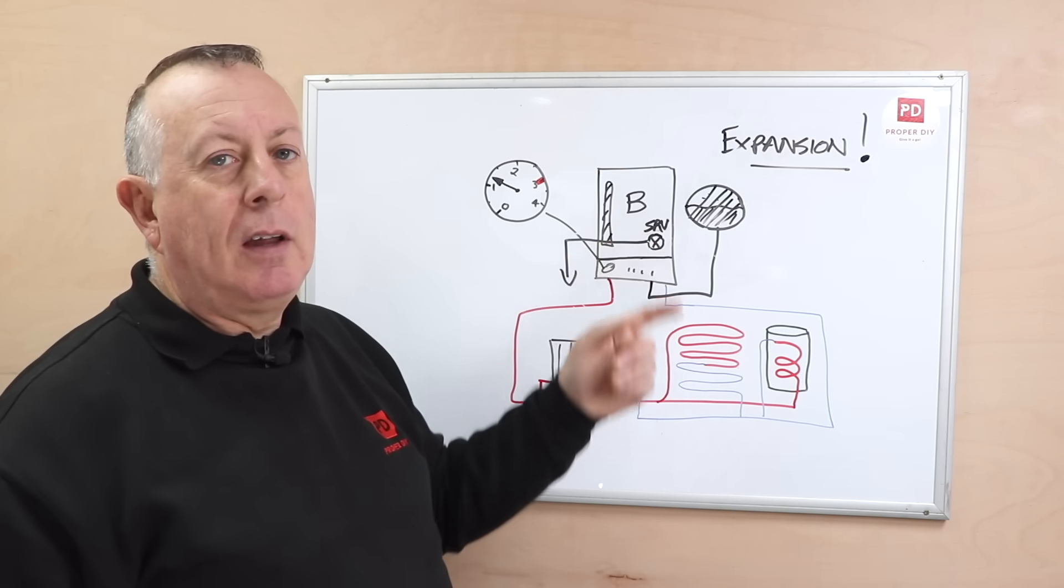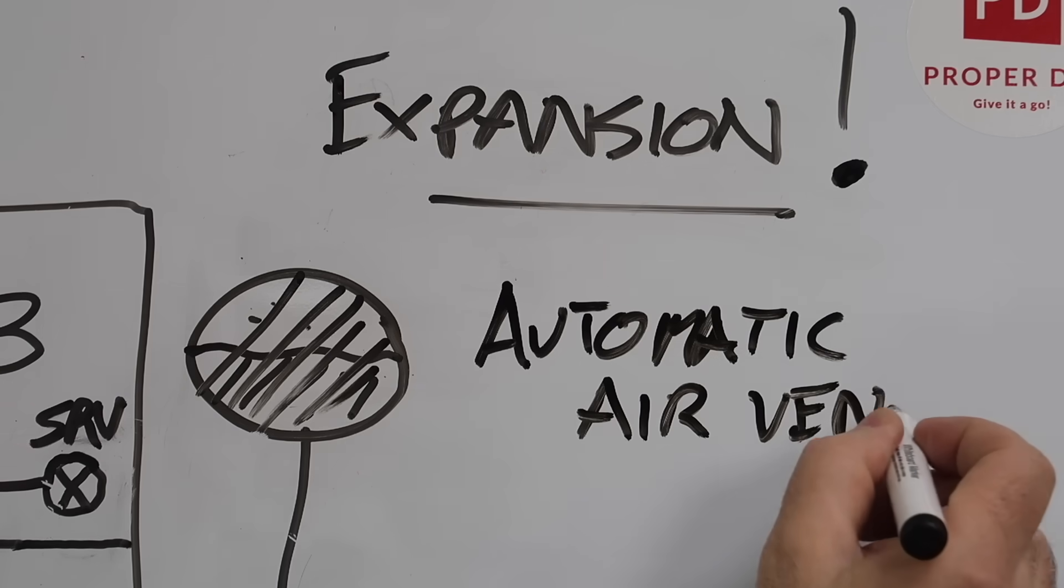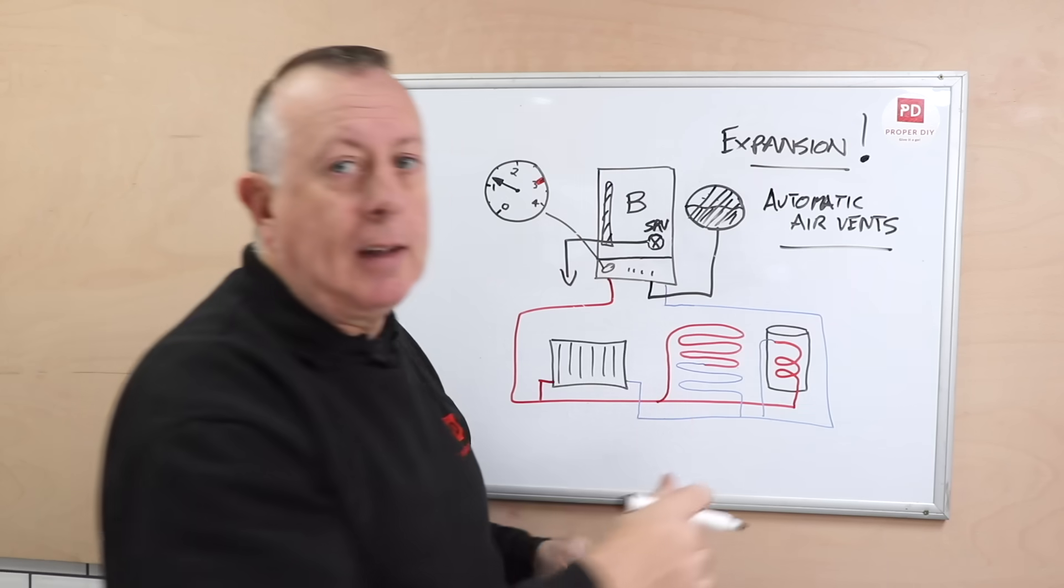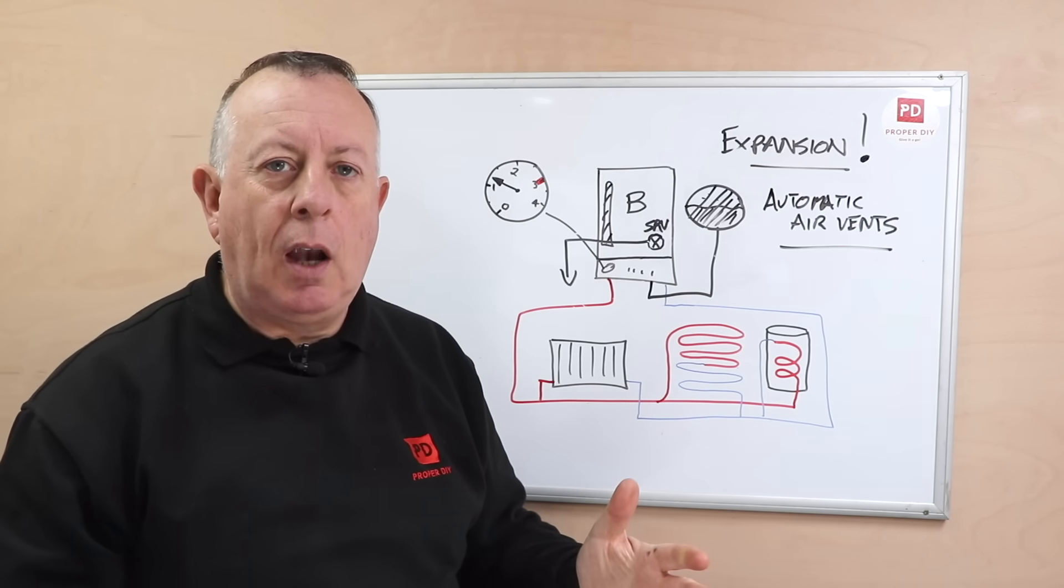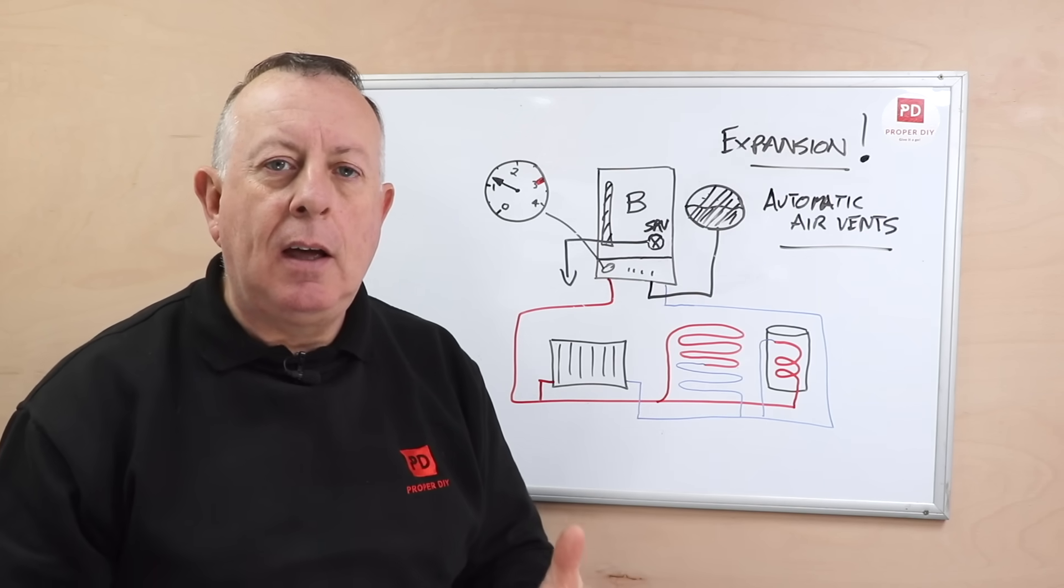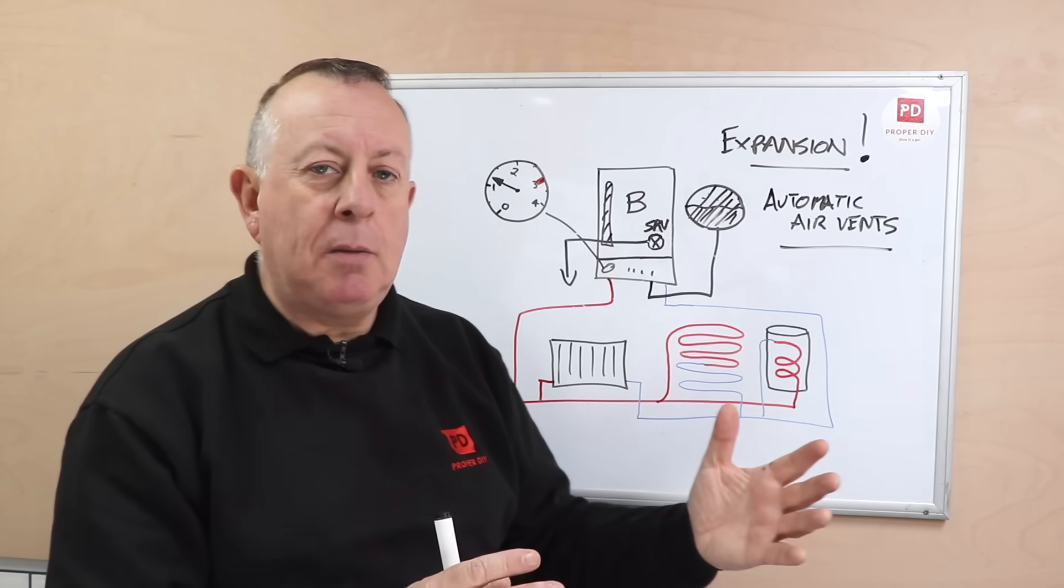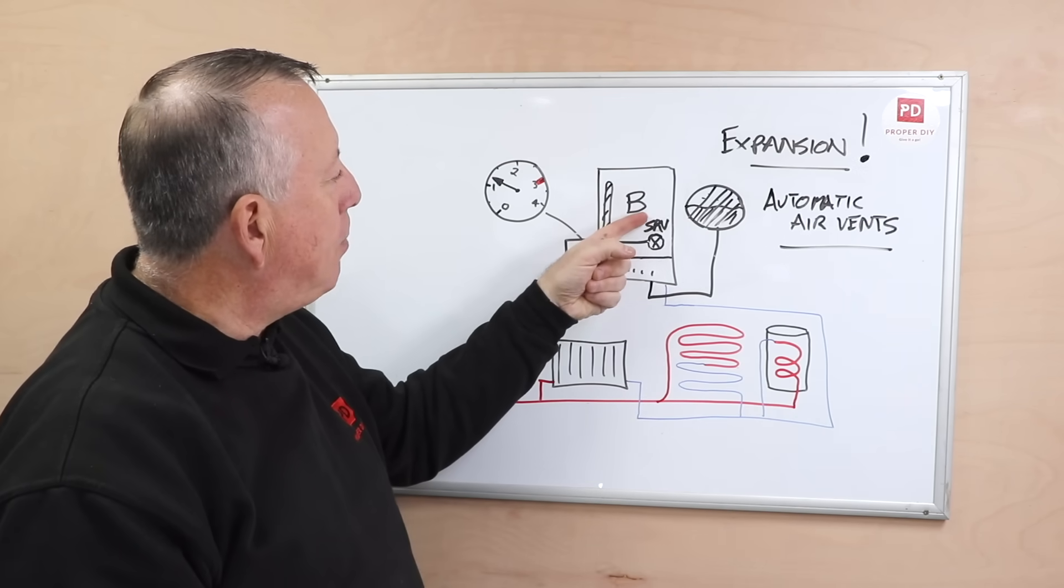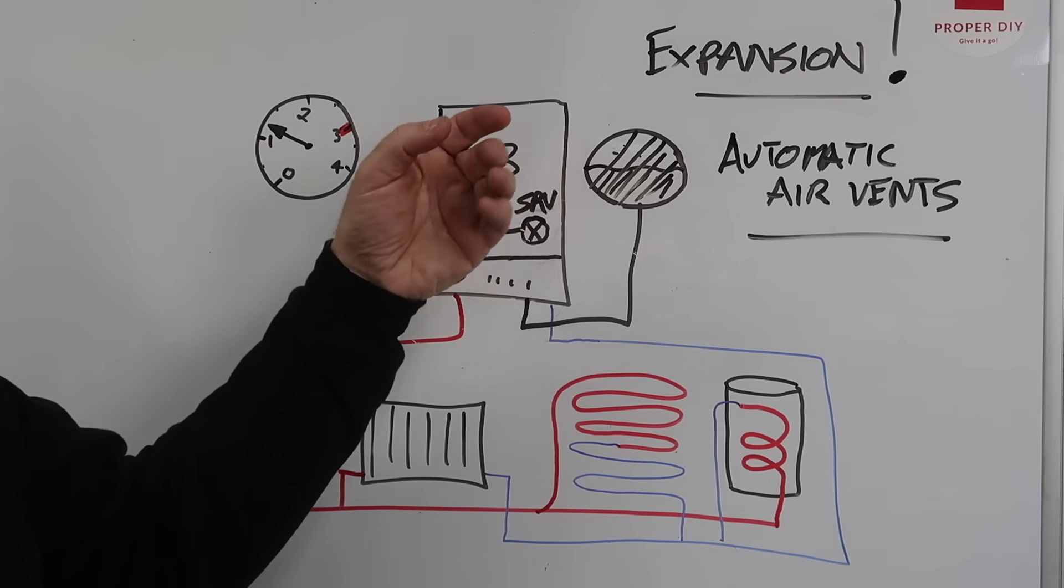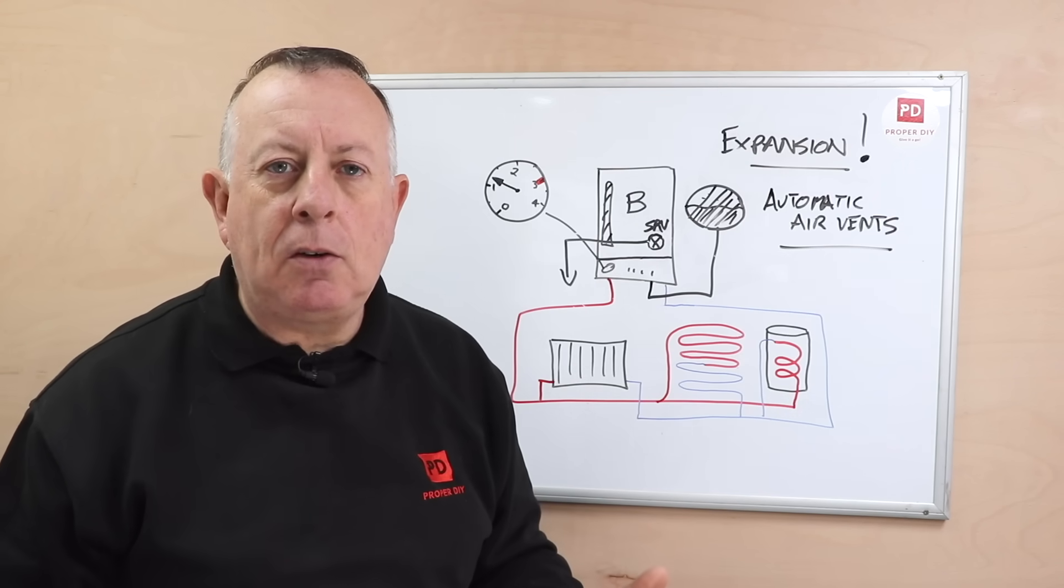Now there is another problem in this boiler that can cause you problems and it's called automatic air vents. Now this is a system within your boiler that dissipates air if it gets trapped in the boiler. It's a bit like having an automatic system that bleeds your radiator but it's in the boiler. So if there is air in the boiler there's a float switch that lets that air out but not the water.